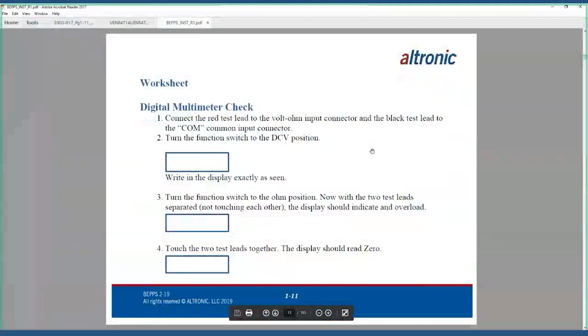So if you connect the red test lead to the main volt-ohm input and the black test lead to the common, turn on the function switch to DC voltage position, and just note what your meter reads, just with the leads not touching anything. And the reason this is a good exercise, it's kind of like a good way to fact check and test your meter. You remember a little while ago I told you I just discovered last week that I had bad test leads on my meter. Well, this is how I verified that.